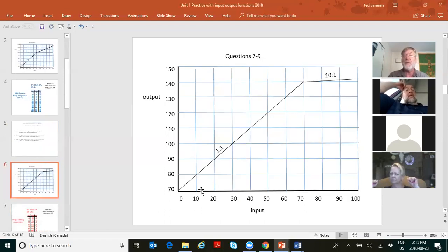So here you go. Here's the hearing aid providing 70 dB of gain. 0 in, 70 out. 10 in, 80 out. 20 in, 90 out. 30 in, 100 out. The gain is 70, 70, 70, 70, constantly. 40 in, 110 out. 50 in, 120 out. Look at this. Oh my God. 70 in is 140 out. Yikes! No hearing aid is doing this. I'm just showing you this to give an idea, okay?